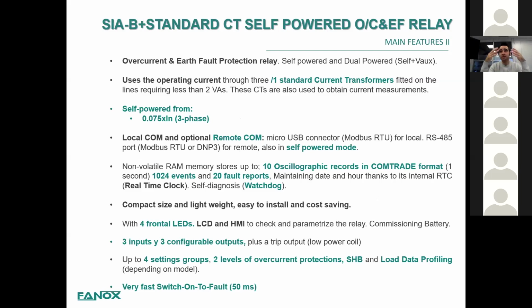As said before, it's a self-power relay, but it's also dual power. It means you can connect it to auxiliary power, and it works with standard CTs with 1 amp on the secondary. It's very important that the requirement to energize this relay is less than 2 VAs, which means that the CTs that you are going to connect to this particular relay have a very compact size. And the self power is from 0.075 times the nominal current. As you can see, it means it's going to be ready for operation at a very low power on your installation.